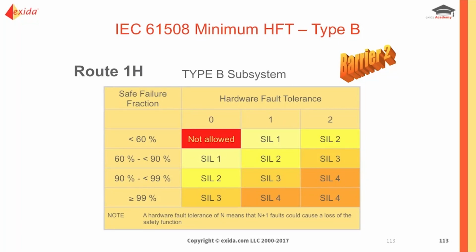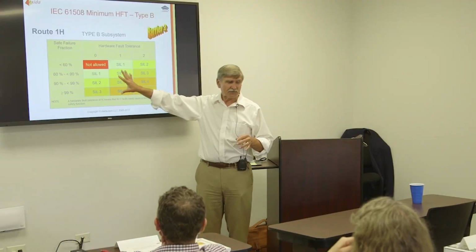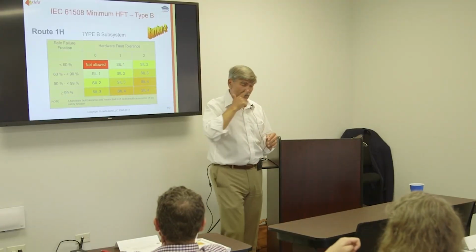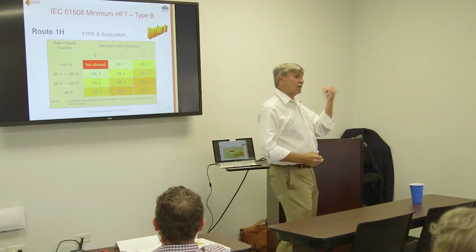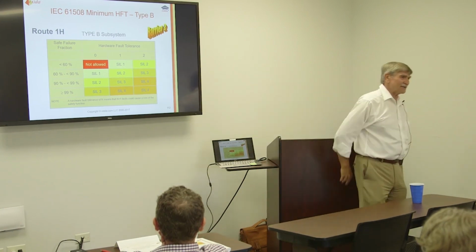In my opinion, you must also design for low false trip rates. And sometimes a trip is a dangerous situation. So the problem with this is these charts tend to push people toward designs with a higher than optimal false trip rate.